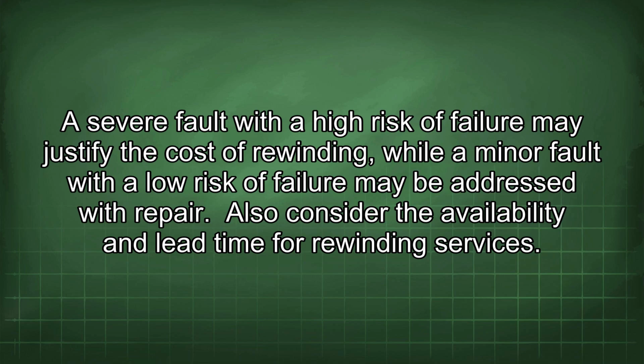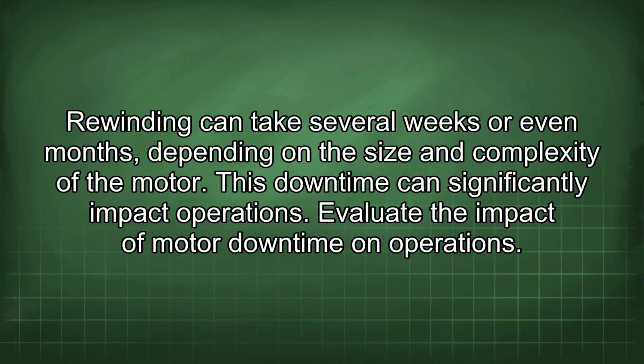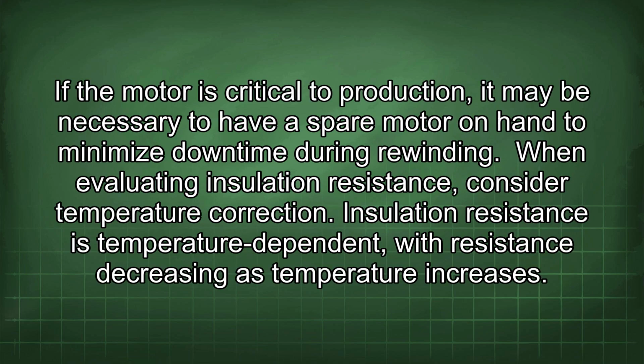Also consider the availability and lead time for rewinding services. Rewinding can take several weeks or even months, depending on the size and complexity of the motor. This downtime can significantly impact operations. Evaluate the impact of motor downtime on operations. If the motor is critical to production, it may be necessary to have a spare motor on hand to minimize downtime during rewinding. When evaluating insulation resistance, consider temperature correction.